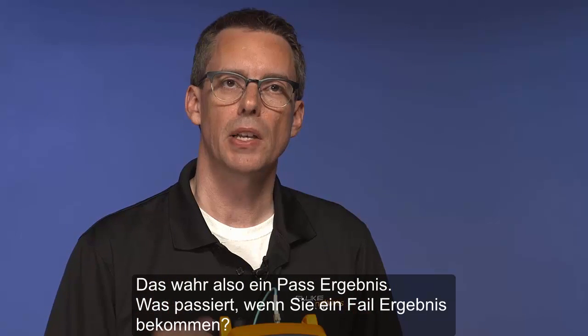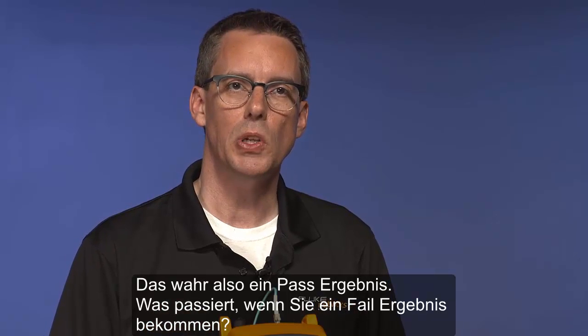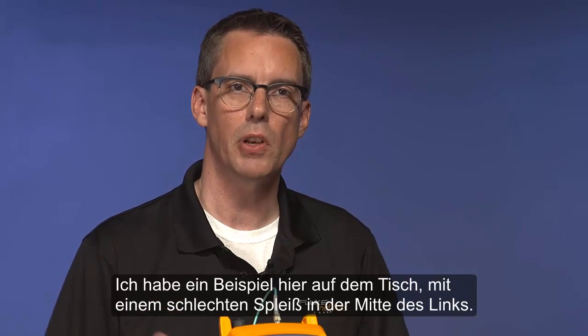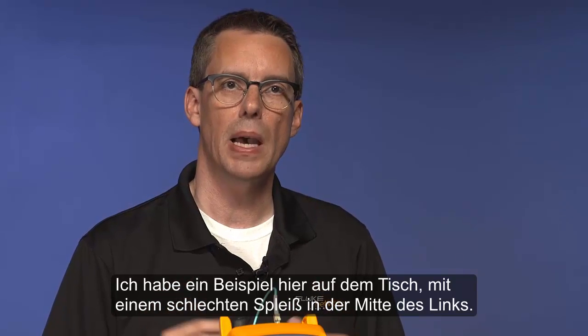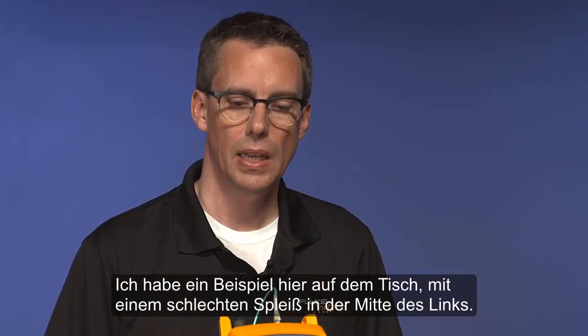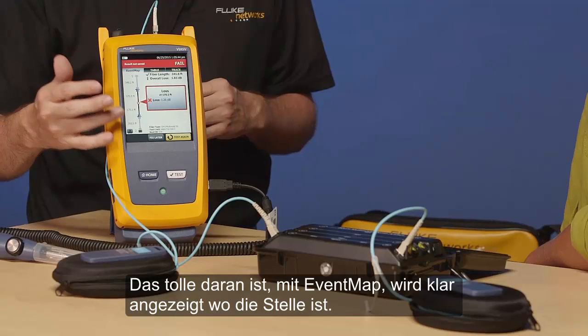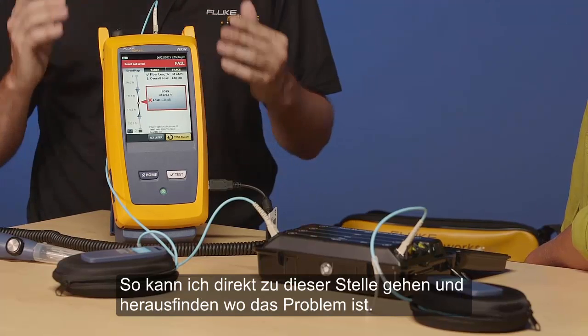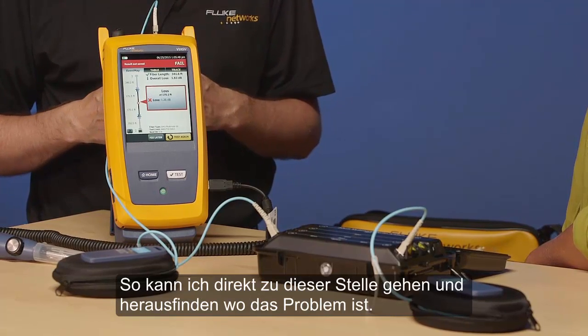So that was a passing test result. What happens when you get a failing result? So an example I've got on the table here is there's a bad splice halfway down the link. And the nice thing is with Event Map, it clearly displays where that is, and I can go straight to that location and figure out what's going on.